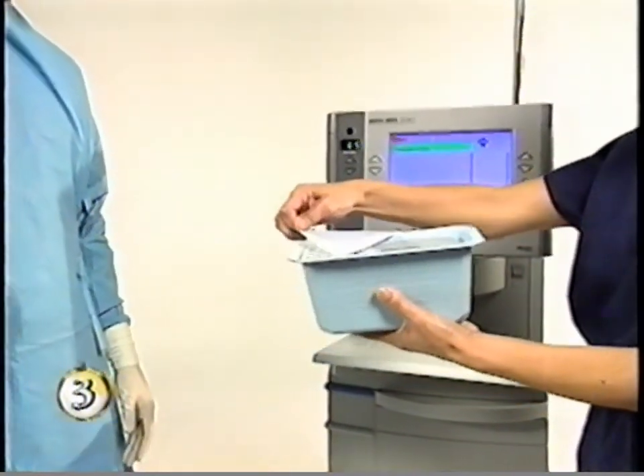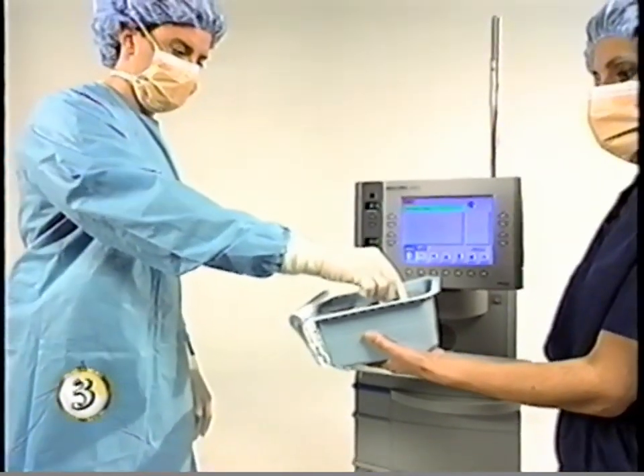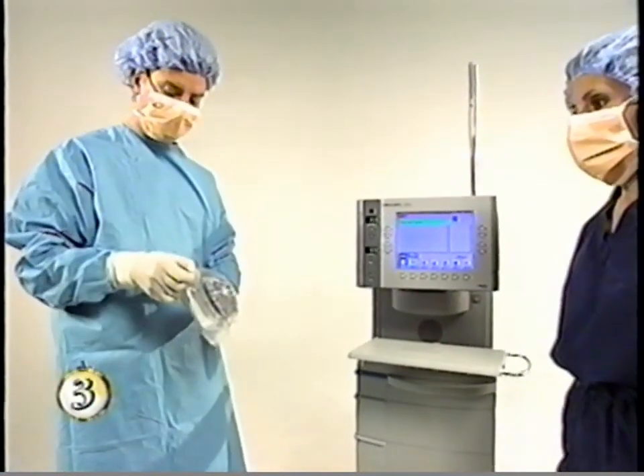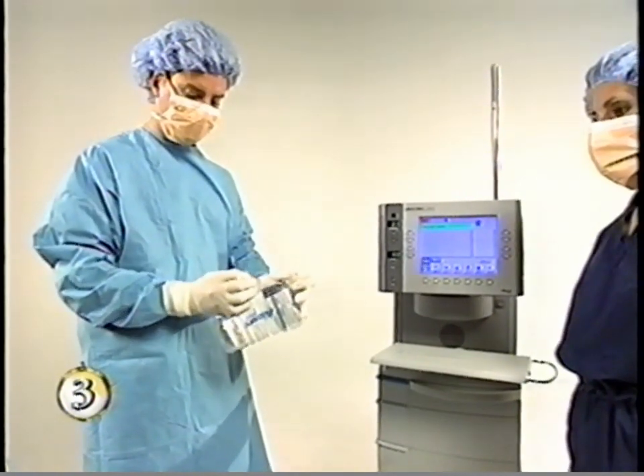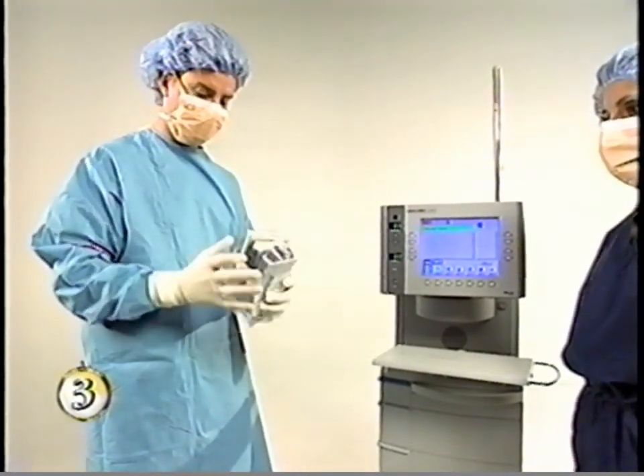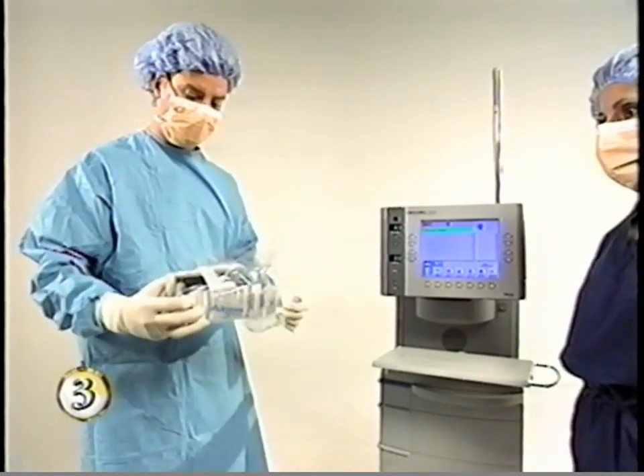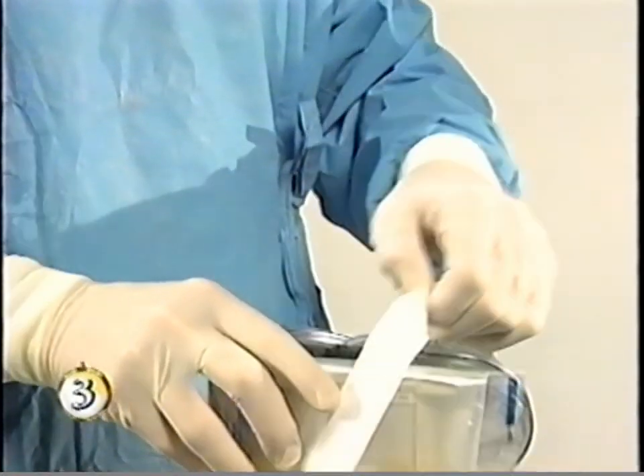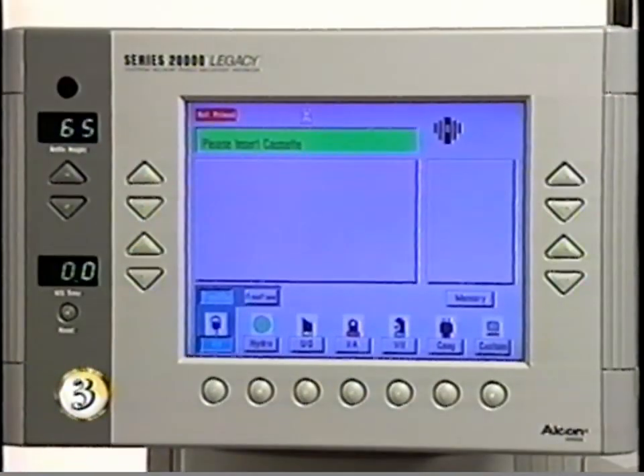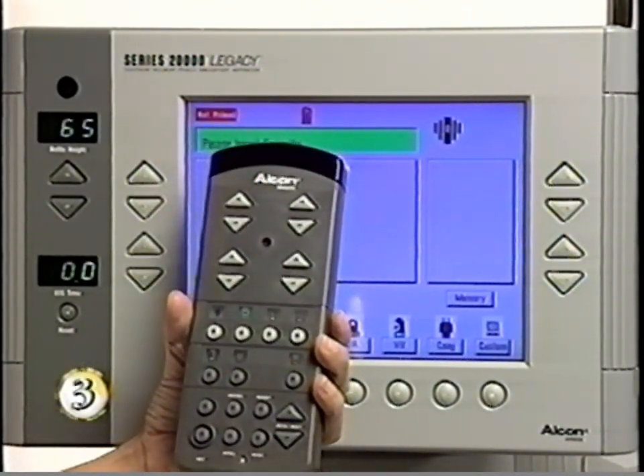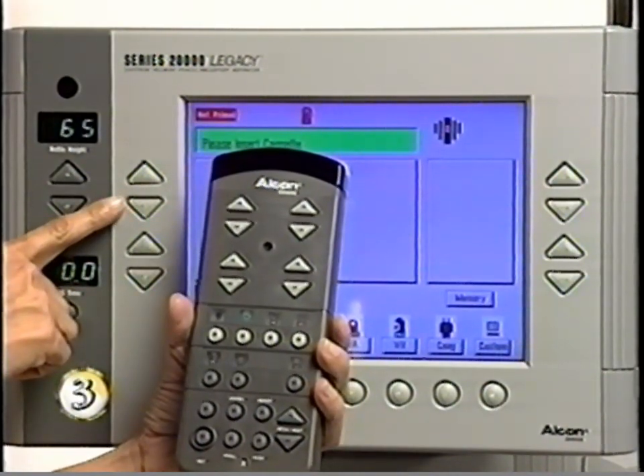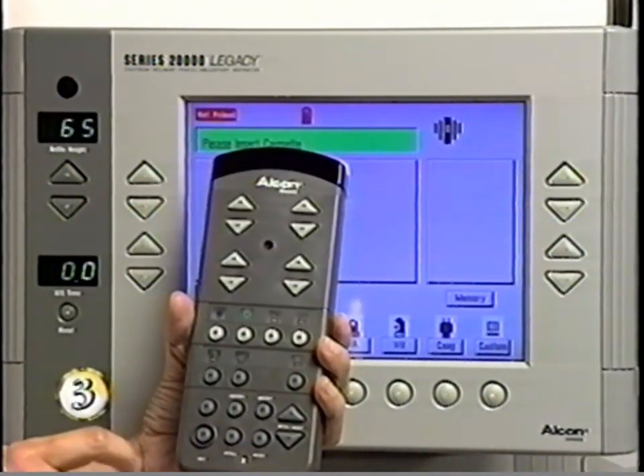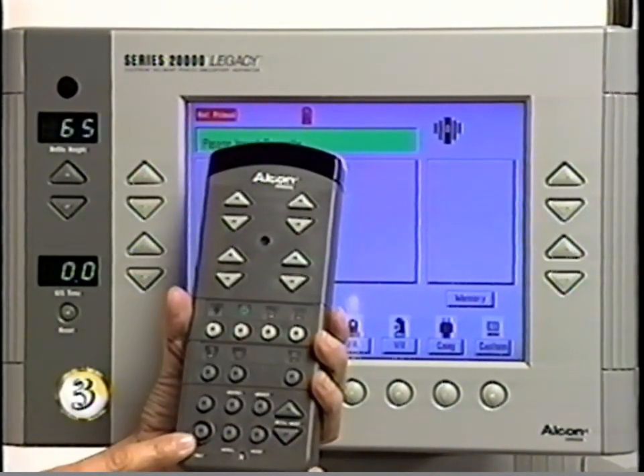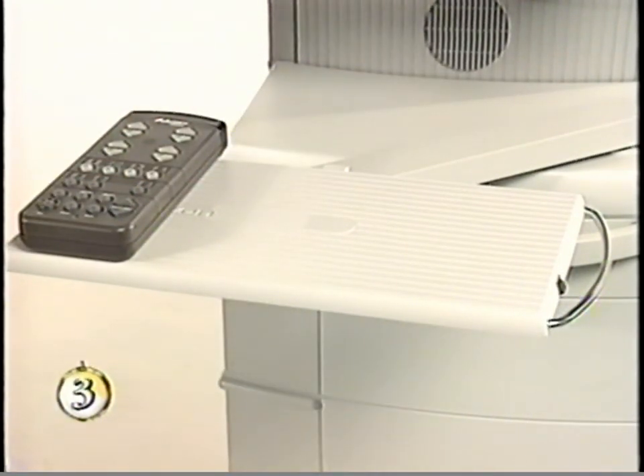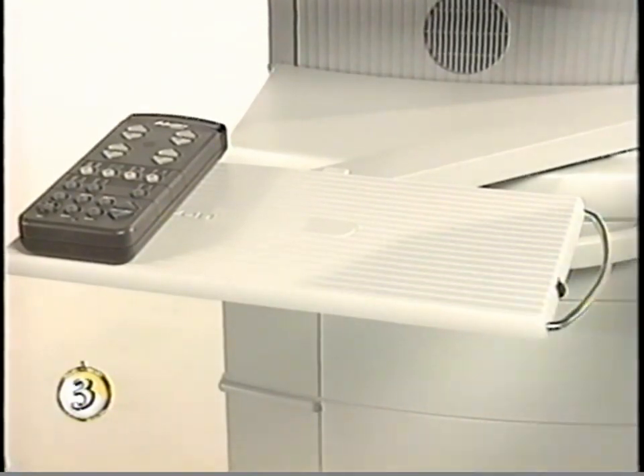After sterilizing the instruments and tray according to hospital procedure, the circulator removes the Series 20000 Legacy cassette pack lid and aseptically transfers the inner bag to the scrub nurse, who opens it and removes its single-use contents. Discard the band surrounding the components. If you plan to use the remote control during surgery, test it first by slightly raising or lowering the IV pole using the bottle height adjustment arrows. To use the remote control from the sterilization tray, the circulator places it on the side of the tray closest to the support tray arm.